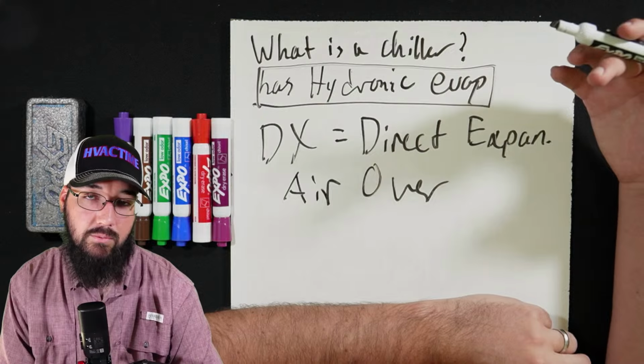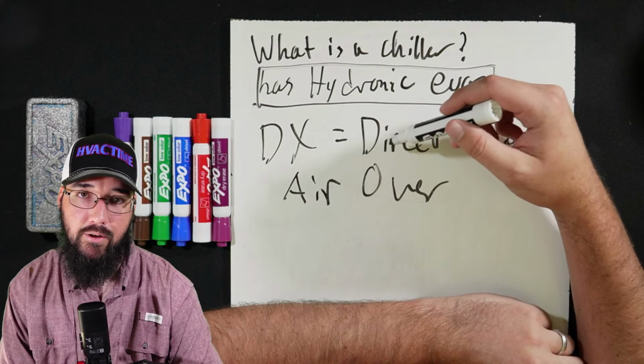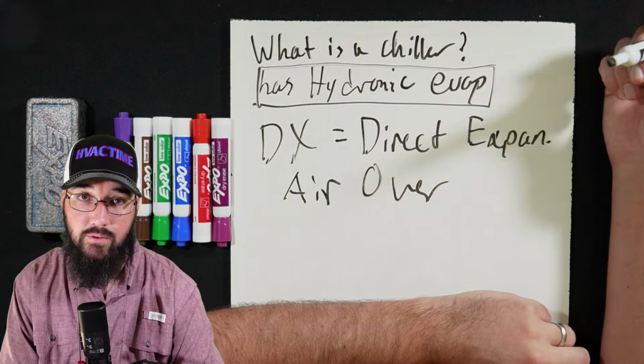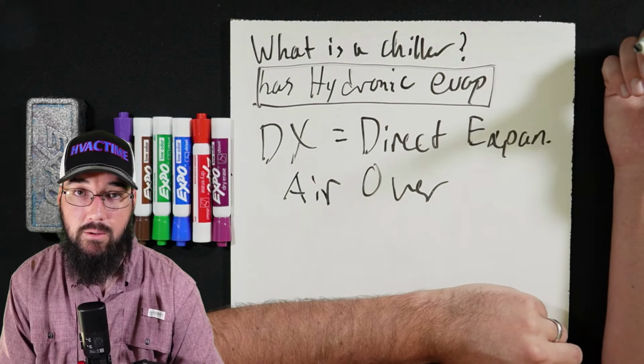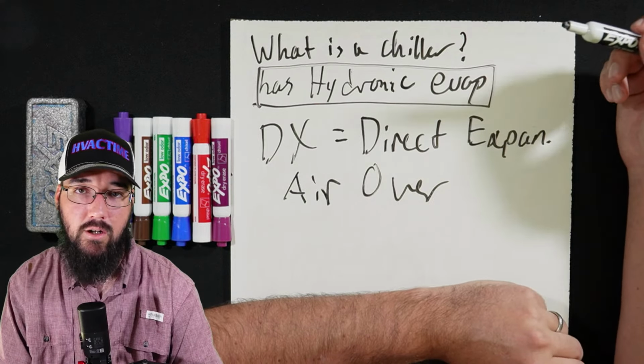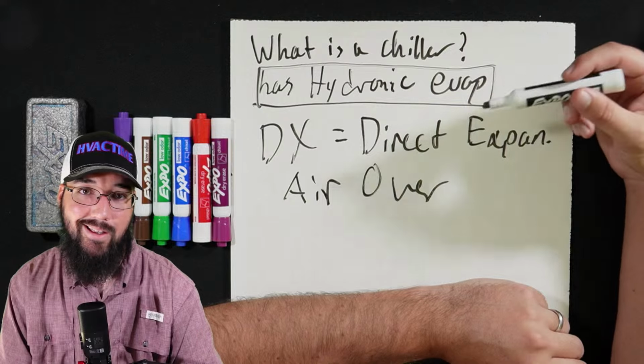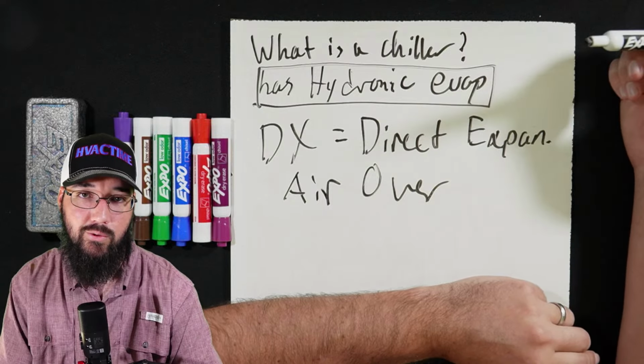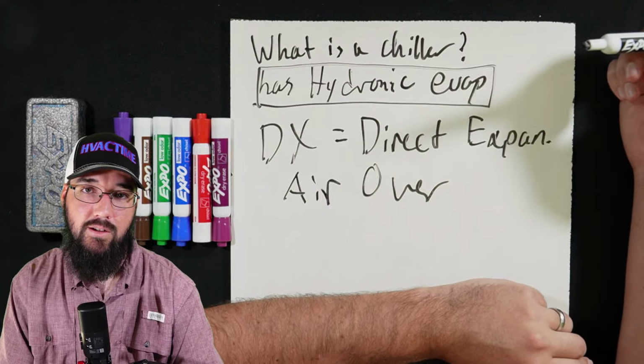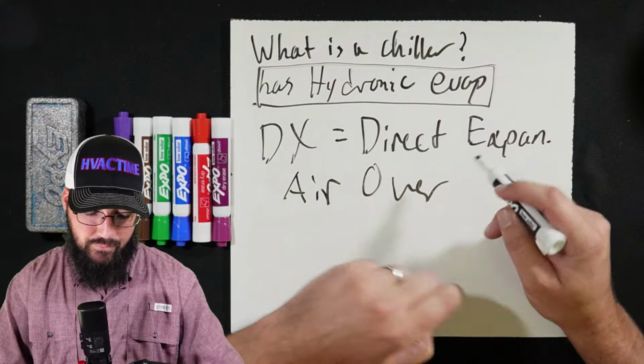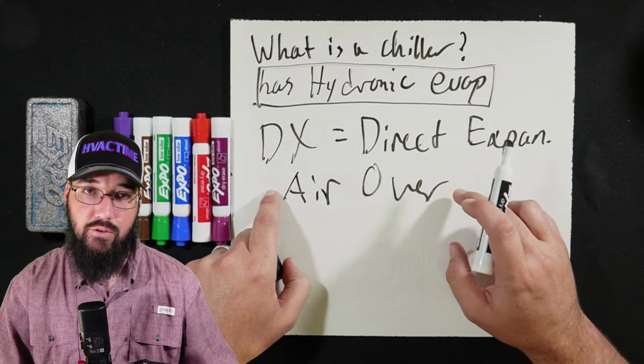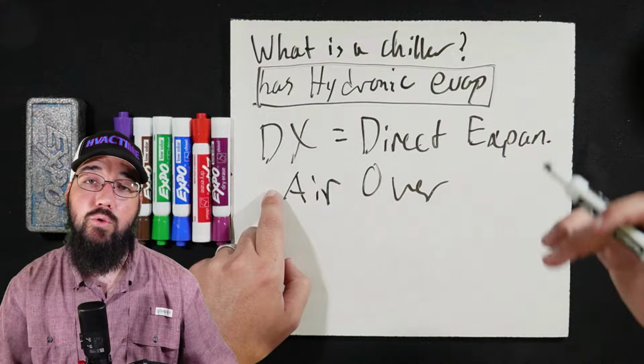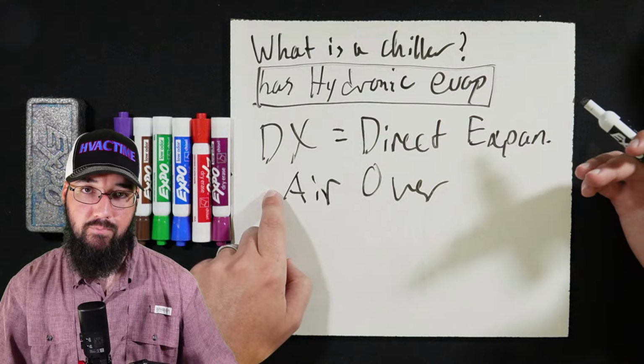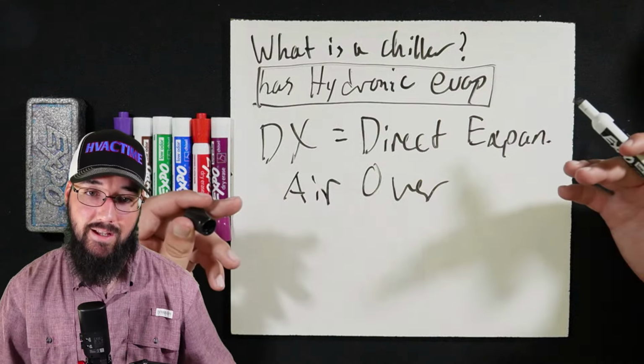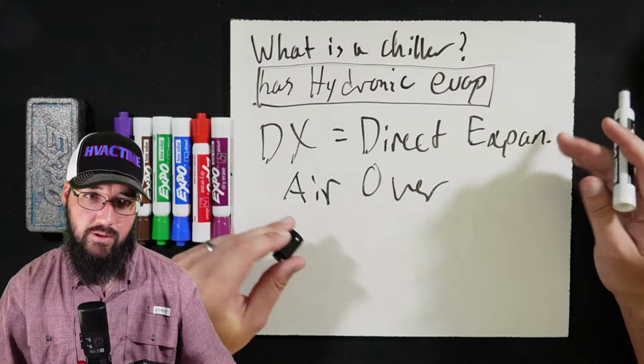There are systems out there that have DX evaporators, but are water-cooled condenser. We call those water-cooled heat pumps in little small office buildings many times. That's a DX unit with a water-cooled condenser. It's DX because we're having a coil that does direct expansion in the coil to the airstream. Hence, we refer to it as a DX, a direct expansion.